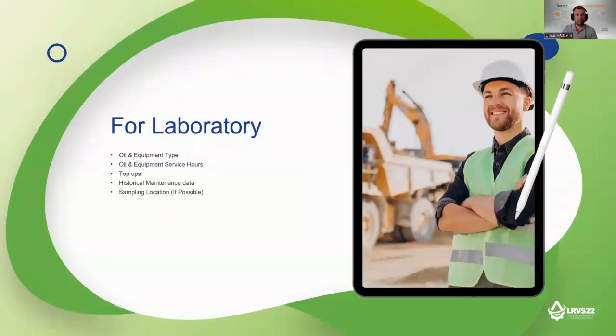We want all types of information for the laboratory, such as oil and equipment type, oil and equipment service hours, top-ups, historical maintenance data, and sampling location, if possible. Oil and equipment type, because we choose the appropriate test suite for the oil and the equipment. We want oil and equipment service hours because we want to define contamination and wear levels. We want the top-ups because if you don't tell the laboratory about topping up, you can see a decrease of the wear levels and contamination levels in the next sample. We need to know that. That's really important.